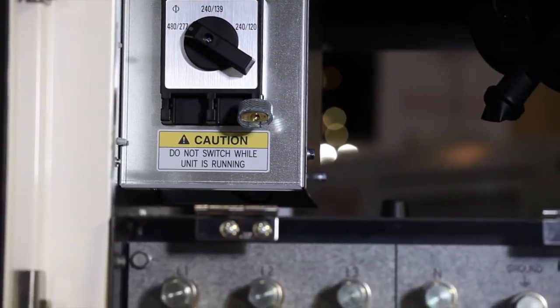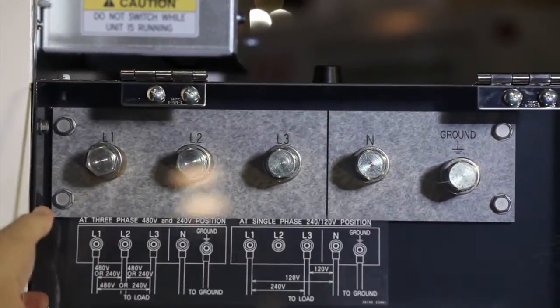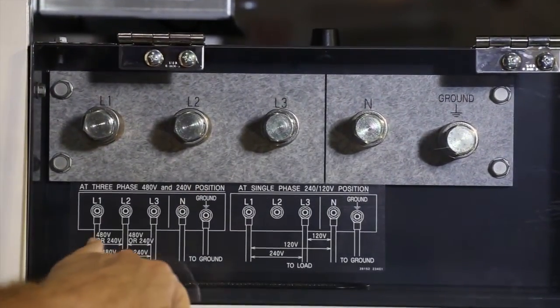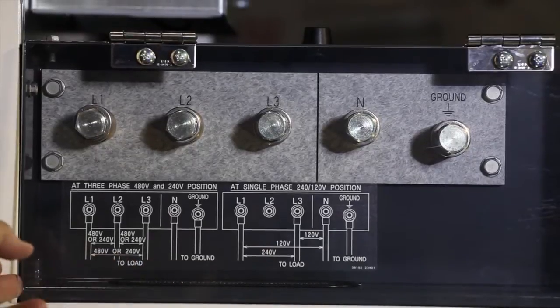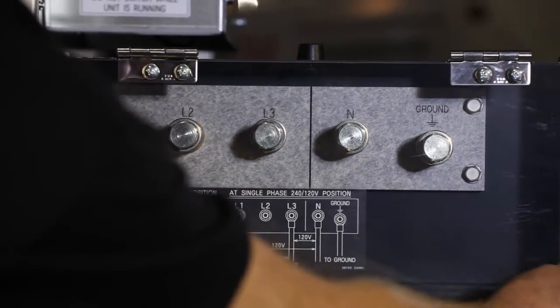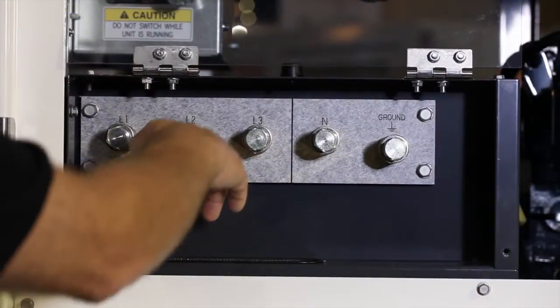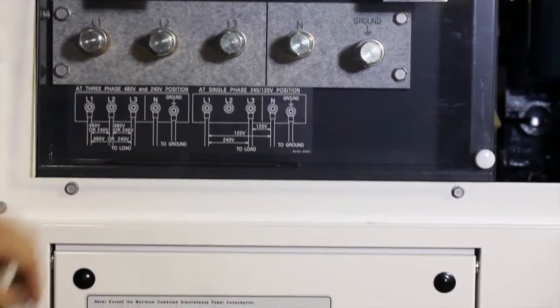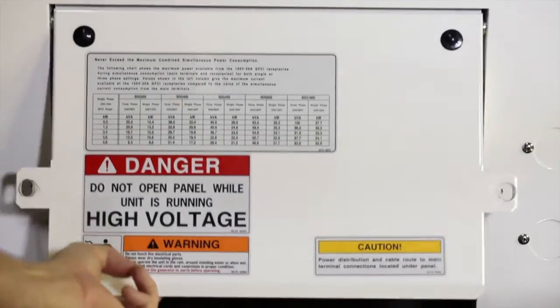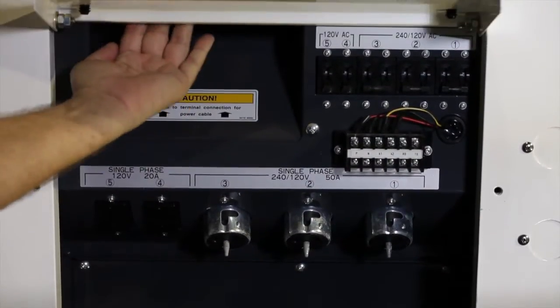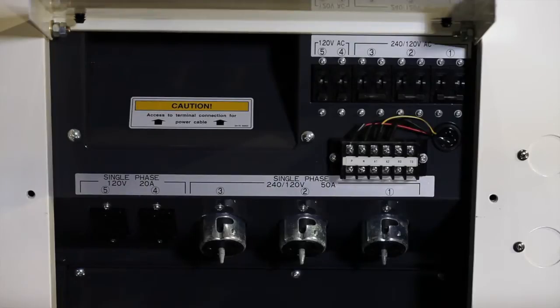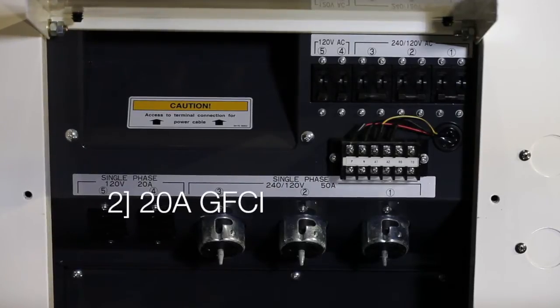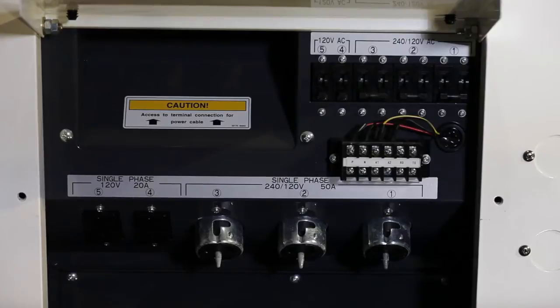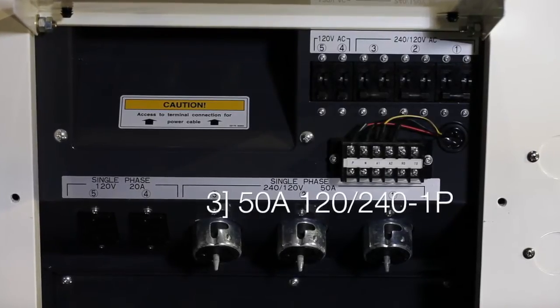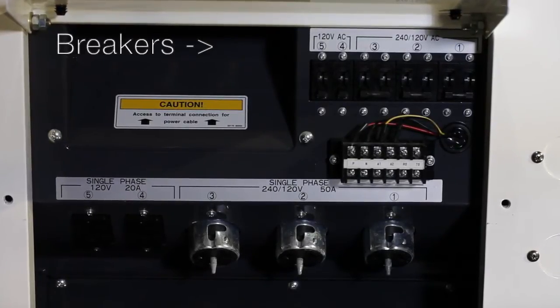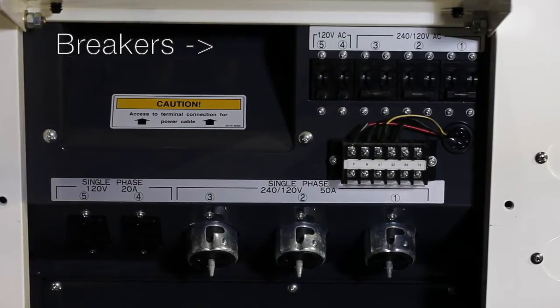The main lug panel is located below the voltage selector switch and is covered by a clear plexiglass panel. Wiring diagrams are printed on this panel to ensure proper hookup. The lug points will accept a variety of cabling up to 4/0. For additional safety, the power cables are fed to the lugs through the accessory panel located below the lug panel and exits to the outside. Also inside the accessory panels are the convenience outlets. There are two 20-amp GFCI protected outlets along with three 50-amp 120/240 volt single-phase twist lock connectors. Each receptacle is protected with its own circuit breaker.